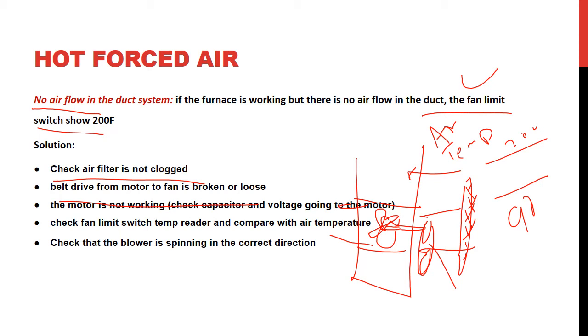It's one of the common problems that the fan is not going in the right direction. Somebody misinstalled the fan, and now instead of pushing, it's pulling. So again, a common problem could be with the motor, also the fan.